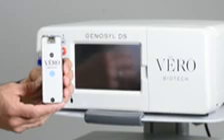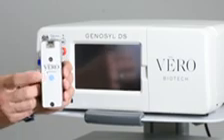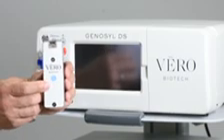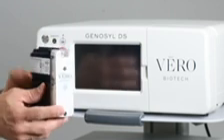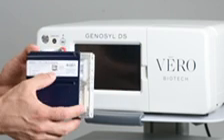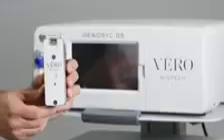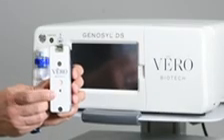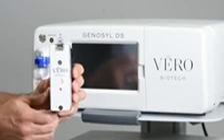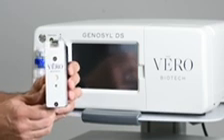The cassette contains the material that will be converted to nitric oxide once it is activated. Confirm the cassette state window is blue. The plastic perforation below the cassette state window has not been punctured, and the expiration date has not passed. If the cassette state window is not blue, or the plastic perforation has been punctured, the material within the cassette has been inerted and cannot dose Genosyl, nitric oxide gas.